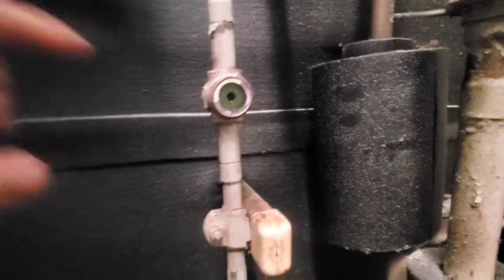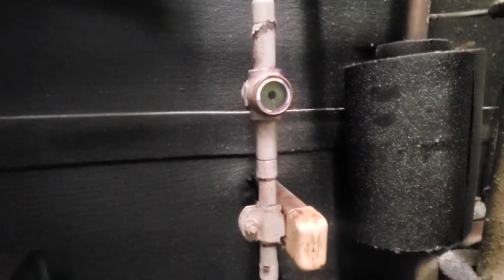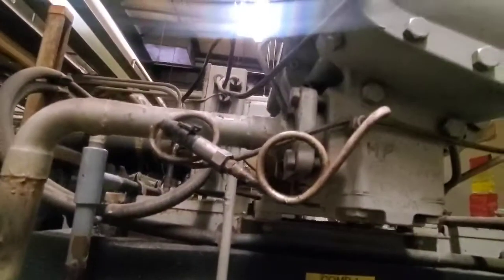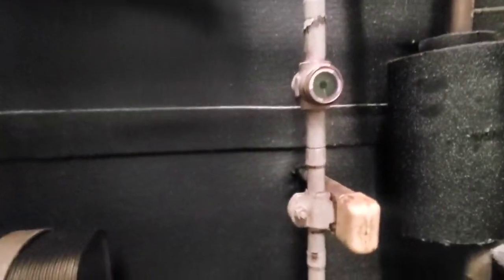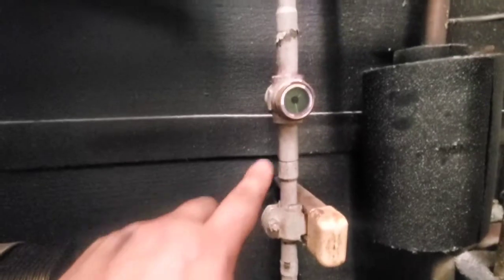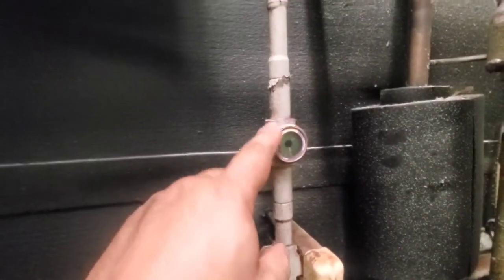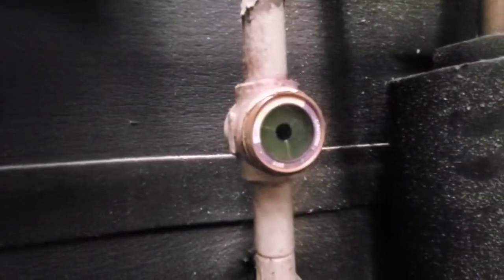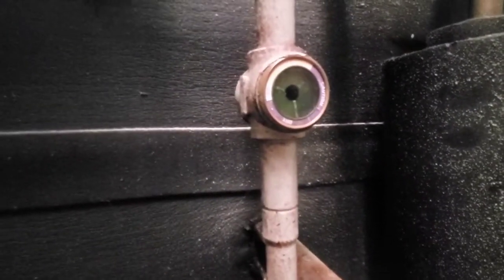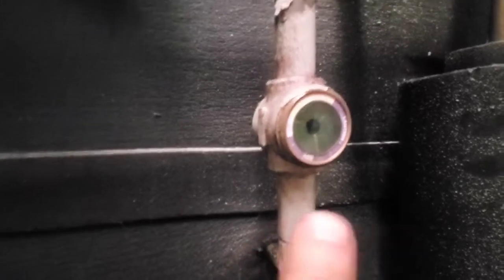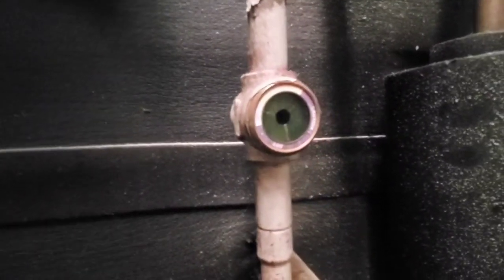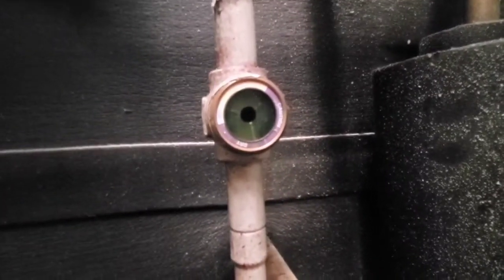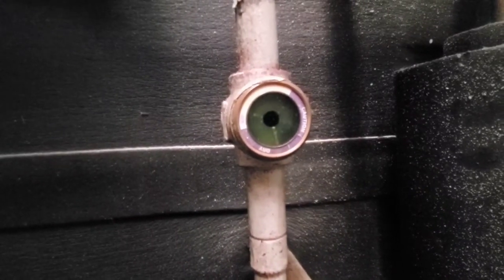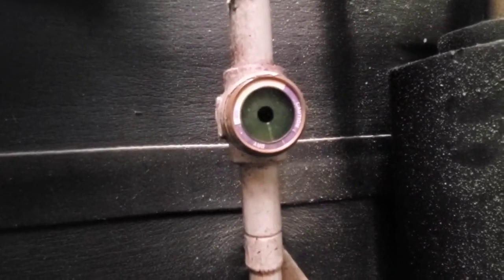Alright, this is the first of two sight glasses that we're looking at here. This is your oil return sight glass. It goes back up to the screw compressor. This solenoid opens up whenever the compressor energizes, and discharge pressure pushes this oil back into the compressor. And we want to see a lot of oil in that sight glass. If we're low on oil, you'll start seeing a bunch of foam in that sight glass, and that's not good. In this case, this is normal oil flow through that sight glass. It's never going to be completely clear.